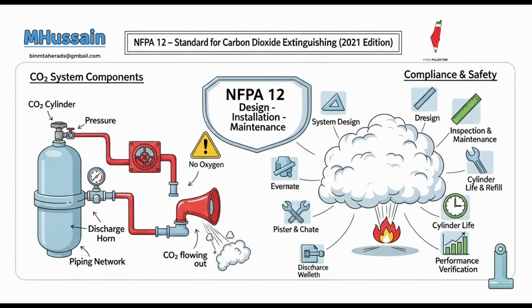This carefully balances the need for rapid fire suppression with the unique life safety and operational demands of a marine vessel, where human presence and the ability to control the ship are paramount. How about manual operation on ships? For manual operation in marine systems, there are also very specific requirements designed to prevent accidental discharge while ensuring availability in an emergency. Generally, two separate valves are required for releasing CO2 into any protected space. Two valves for manual release.